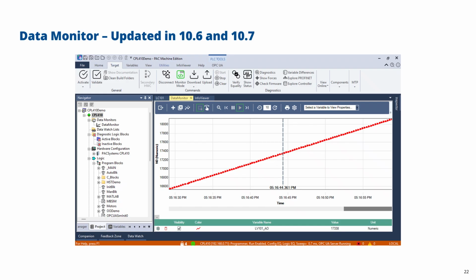So for example, if you want to trend a value while tuning a PID loop, or controlling some sort of analog device, you can go into your data monitor inside the project tab. You can create a new data monitor window, then drag and drop variables from the variable list onto that data monitor. When that data monitor is running, it records all of those variables onto a trend window.